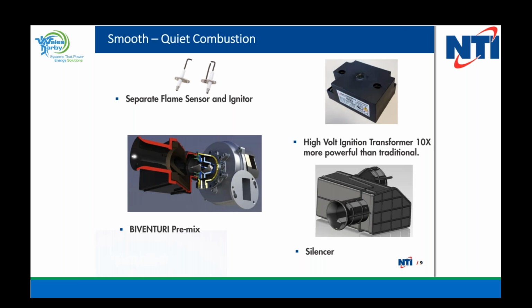Absolutely. One of the things we have found a lot of times, especially with the igniters, if you inherited a job, maybe you've taken over service on a particular install, and you notice that there's multiple igniters laying on the ground. That's a venting issue, gentlemen. Those igniters fail because the venting is not correct, and we're sucking in some exhaust, we're bringing in moisture, and we end up killing those igniters. So as we always say, a good install will stop 99% of your maintenance issues.